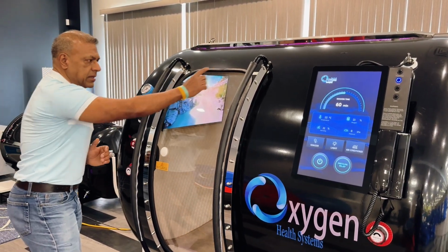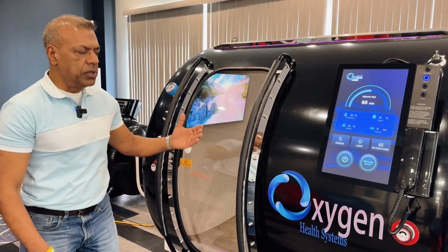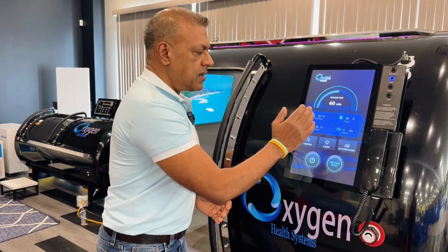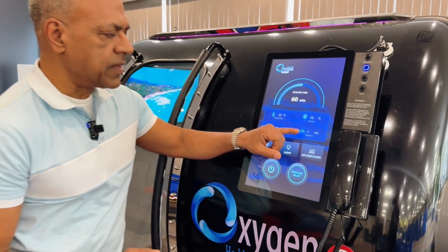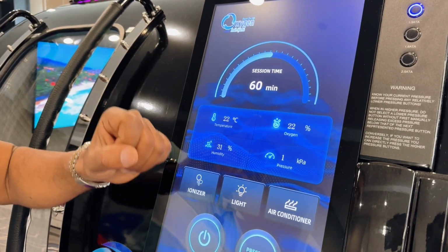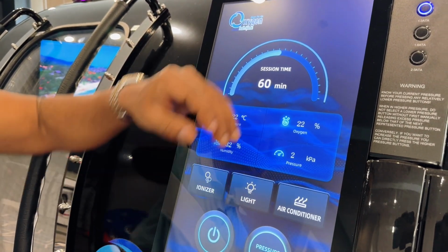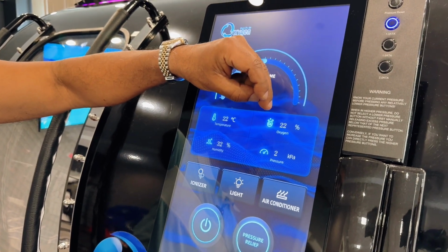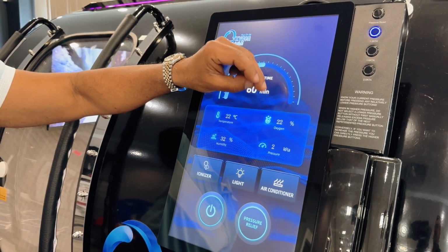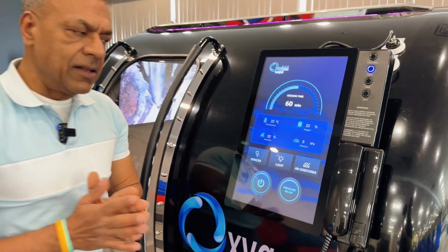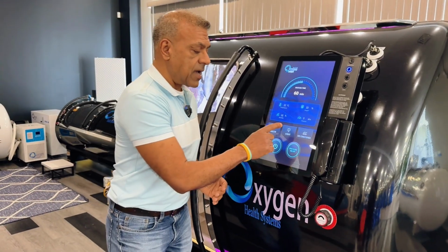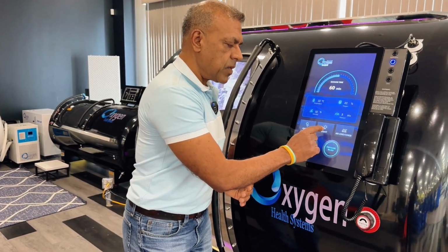door pushed against the door seal, and we will notice in just a few seconds that the pressure will rise, such as right now the pressure is 1 kilopascal. It should go up to 2 in just a few seconds. There you go. And I'm also beginning to notice that my oxygen concentration too is rising from 21 at sea level to 22%.